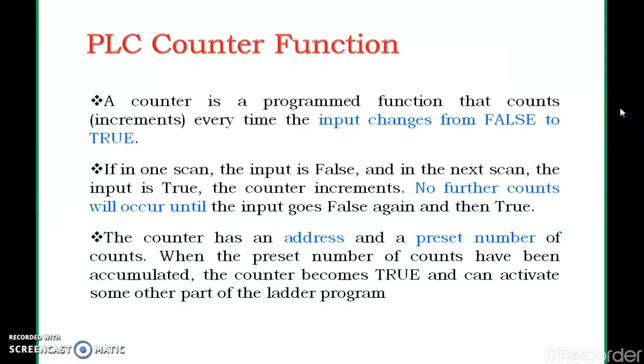Key facts about counter function: a counter counts every increment when the input changes from false to true. If in one scan the input is false and in the next scan it is true, the counter increments. No further count occurs until the input goes false again and then true. Every counter has an address and a preset number. When the preset number of counts have been accumulated, the counter's done bit becomes true and it can activate the next part of the ladder diagram.